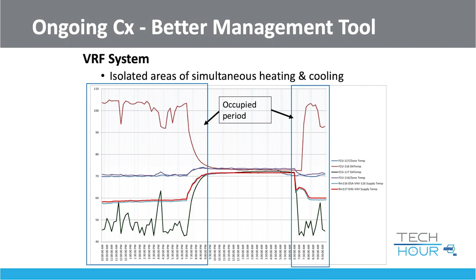Here's a dedicated outside air unit. It's got 5 separate stages of DX cooling in it with non-interlaced coils and dampers. What you see in the spikes is the operation of each of the 5 cycles ramping up and down, because there's stratification in the unit.